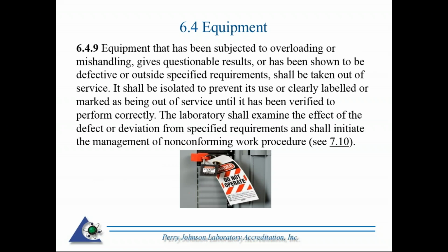Nothing new here. Any equipment that has been subjected to overloading or mishandling, gives questionable results, or has been shown to be defective or outside specified requirements shall be taken out of service. It shall be isolated to prevent its use or clearly labeled and marked as being out of service until it has been verified to perform correctly.